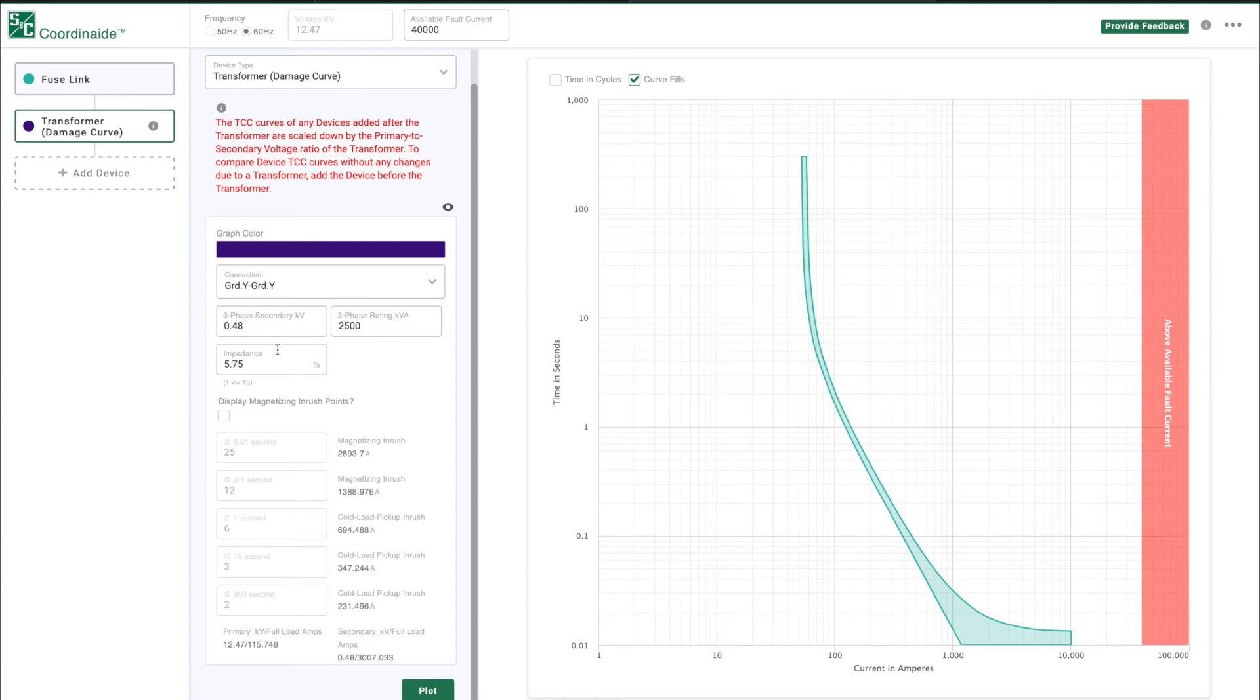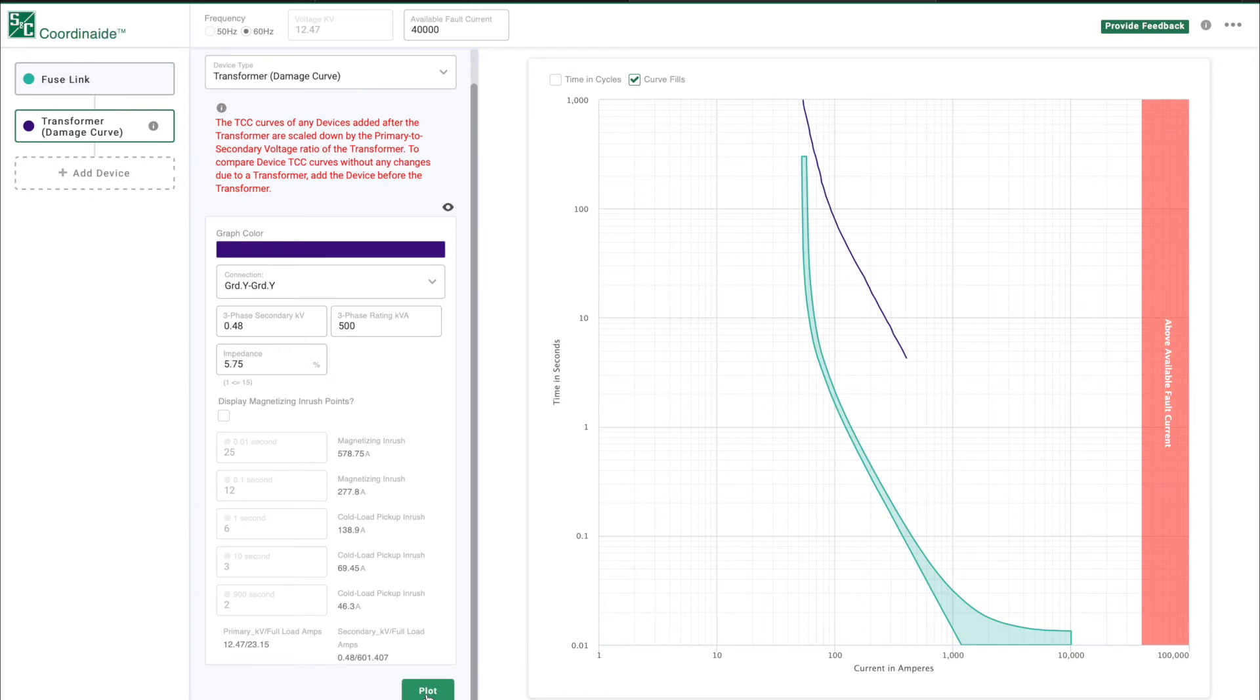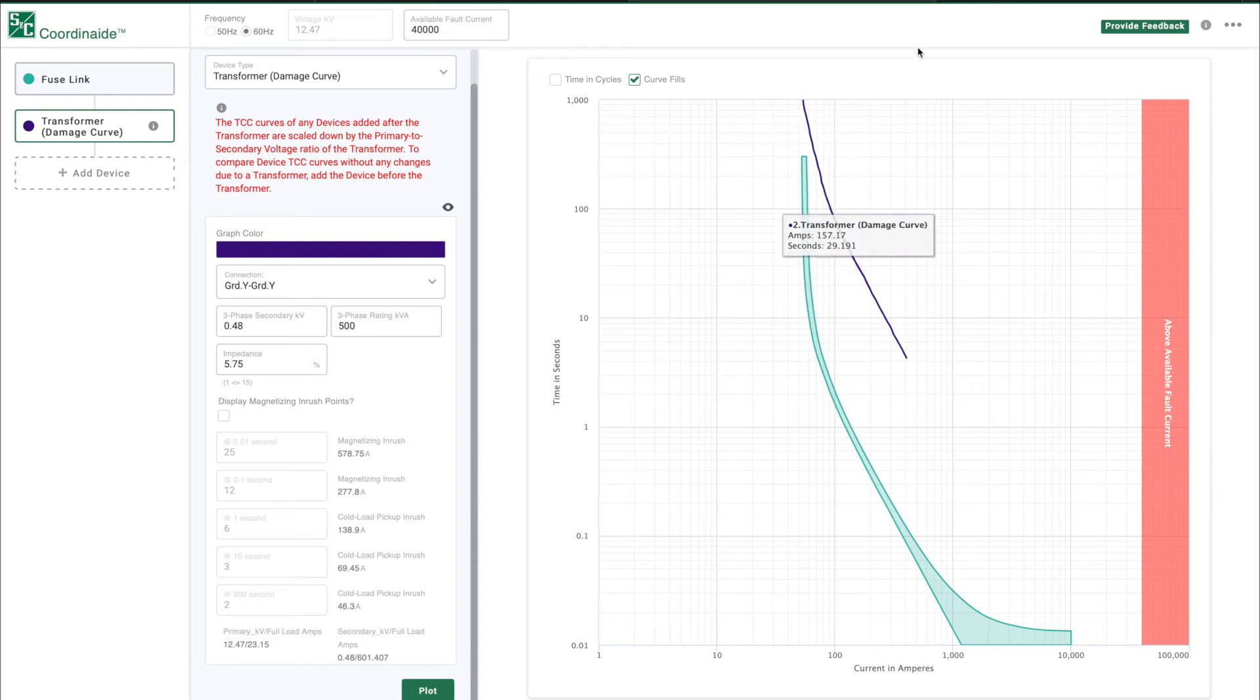And let's leave the three-phase secondary at 0.48 and the impedance at 5.75. Of course, you'll need to use the actual specifications of your transformer. Now click on the plot button and see the damage curve. So in this case, you can see our fuse will successfully protect the transformer because it will operate before the current reaches a level that is damaging to the transformer.